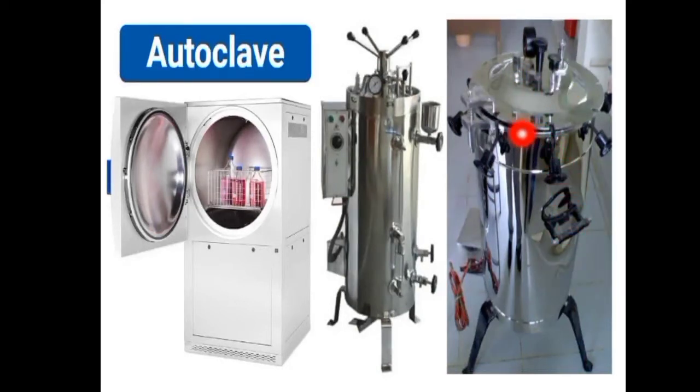Here the cylinder contains water up to a certain level, and the articles to be sterilized are placed on the diaphragm, serving as a platform situated above the water level. Heating can be done either by gas burner or by electricity. The chamber is furnished with a steam tap at the top and a pressure gauge with a safety valve.